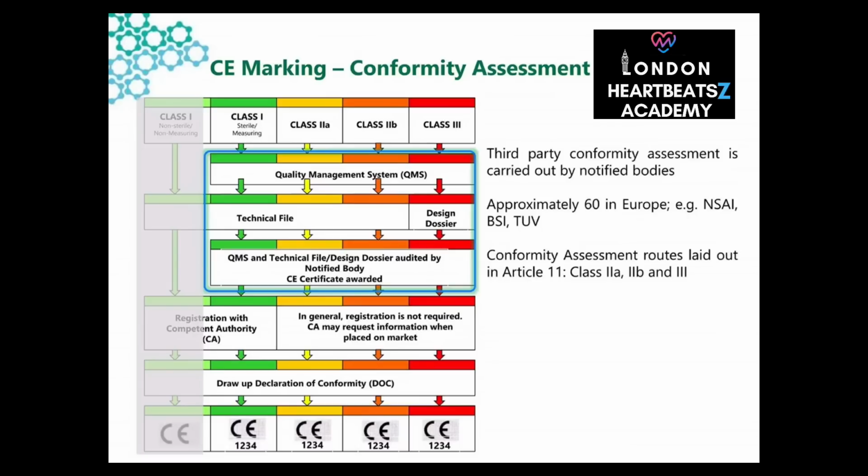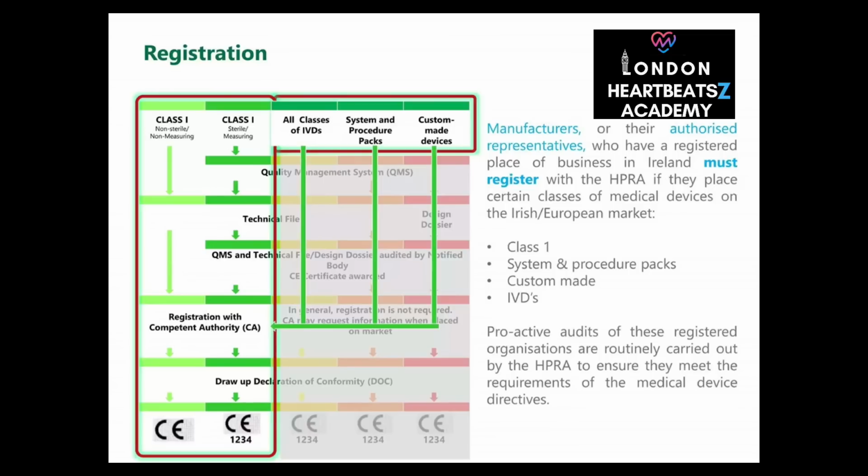Yes, exactly. So how does a developer go about getting that? Well, it depends on the classification of the device. For Class I devices, manufacturers can self-declare conformity. So they just check their own work. Essentially, yes. They assess their product against the essential requirements, draw up a declaration of conformity, and affix the CE marking. Is there a catch? Well, even for Class I devices, if they are sterile or have a measuring function, like a thermometer, they require a notified body to assess those specific aspects. So there's still some oversight, even for the lowest risk devices.